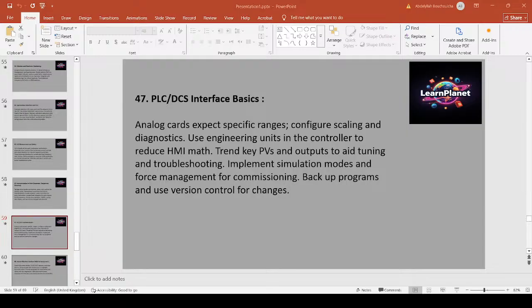Analog I/O card expects specific ranges and configuration. Set input type, wiring, filter, and scaling in both hardware and software. Keep engineering units in control tags to avoid HMI math errors and accidental operator misinterpretation. Implement simulation modes and force management tools for safe commissioning and maintenance. Back up programs and use version control with rollback capability. Example: before commissioning, ensure the pressure transmitter input card is configured for 4 to 20 milliamps with proper filtering and tag scaling to bar on the PLC.